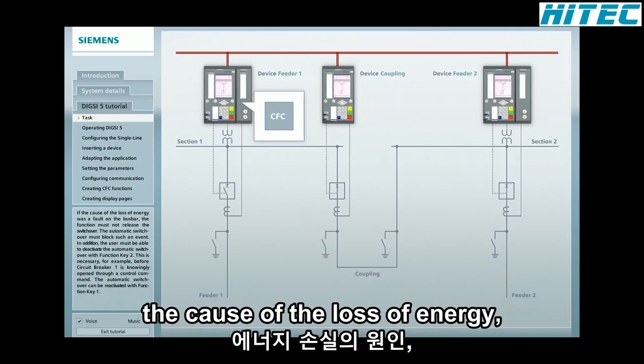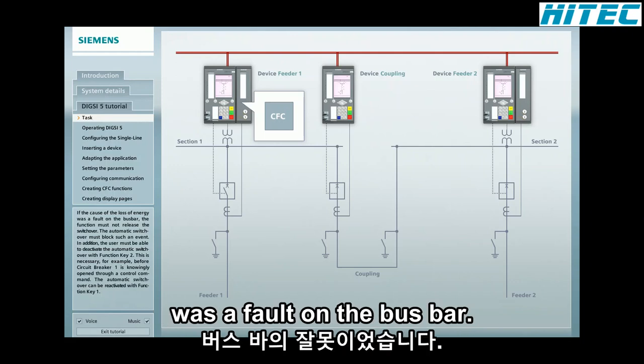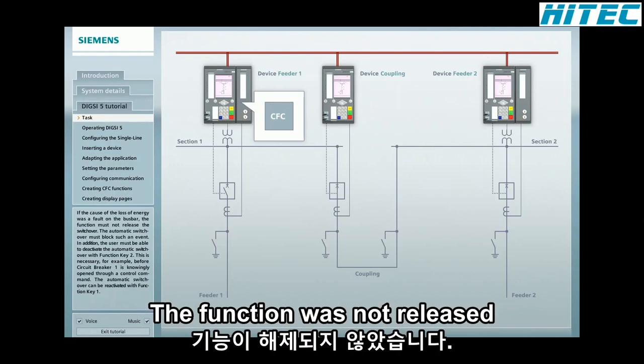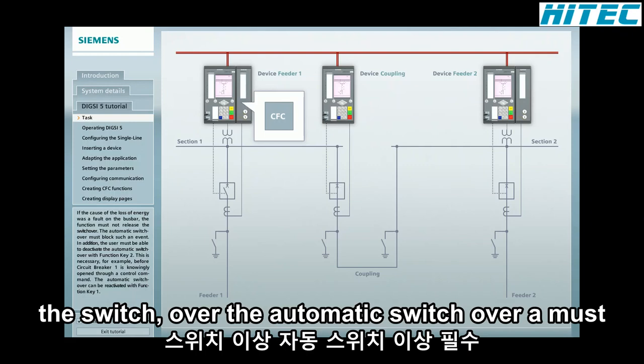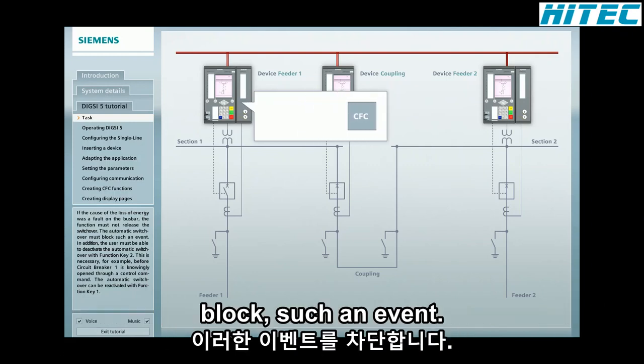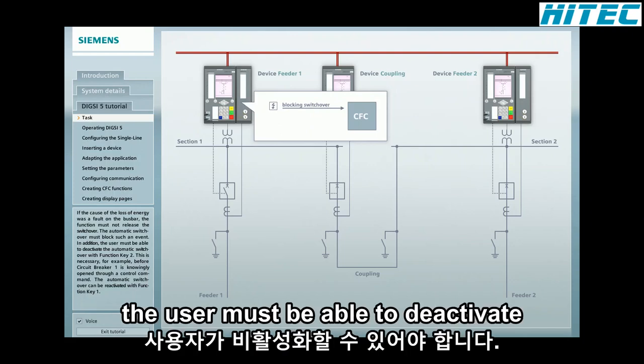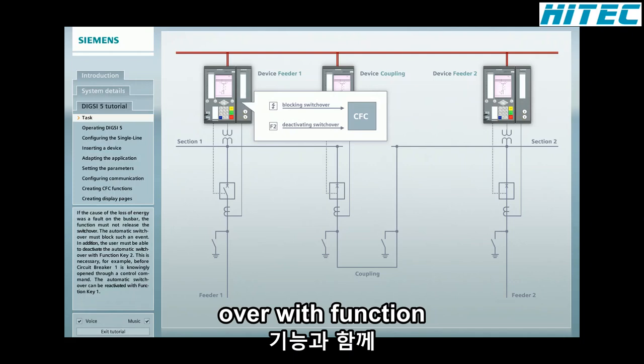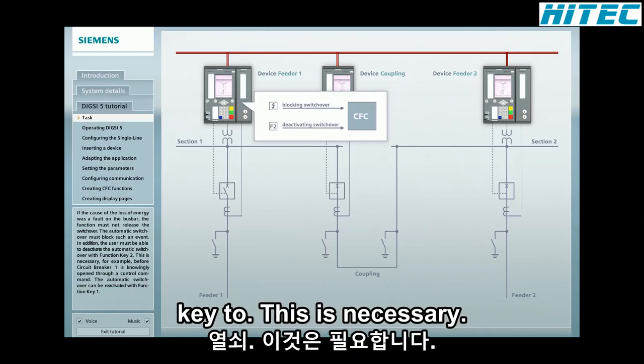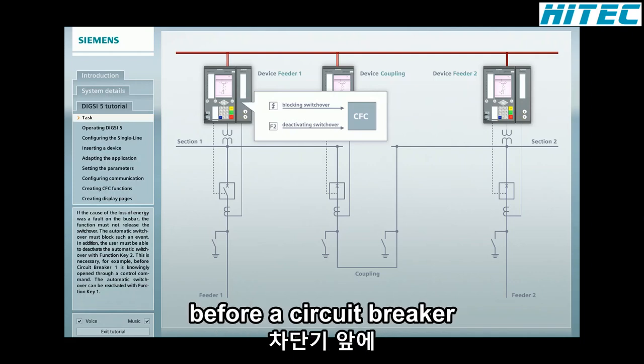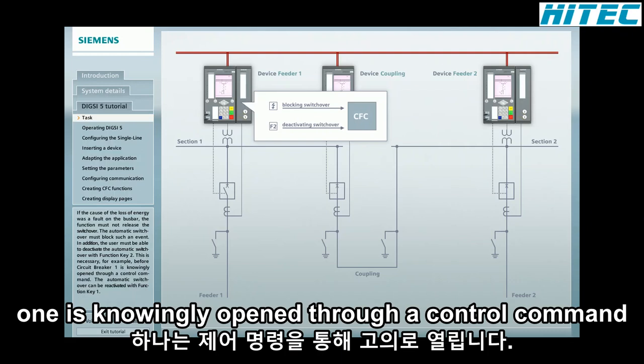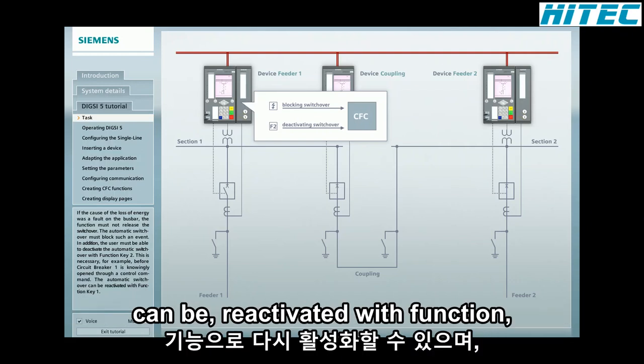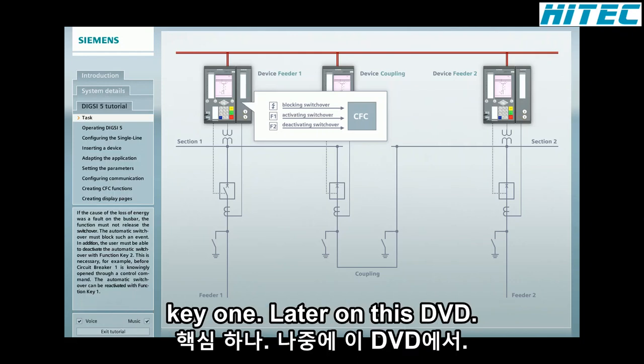If the cause of the loss of energy was a fault on the busbar, the function must not release the switchover. The automatic switchover must block such an event. In addition, the user must be able to deactivate the automatic switchover with function key 2. This is necessary, for example, before circuit breaker 1 is knowingly opened through a control command. The automatic switchover can be reactivated with function key 1.